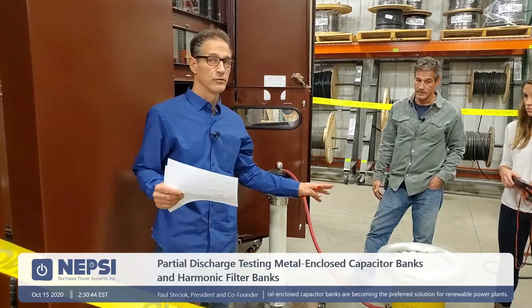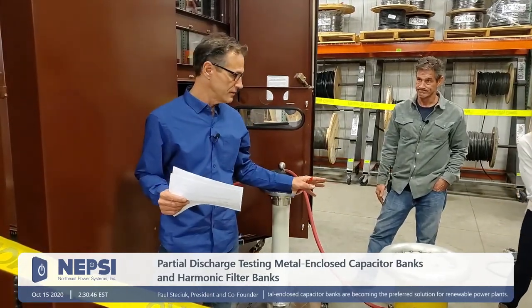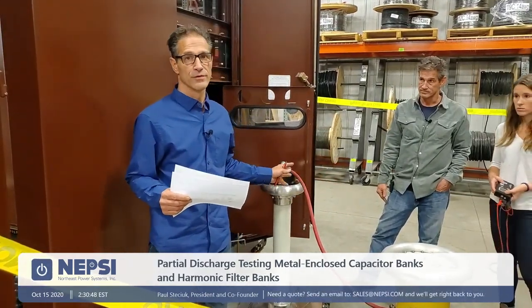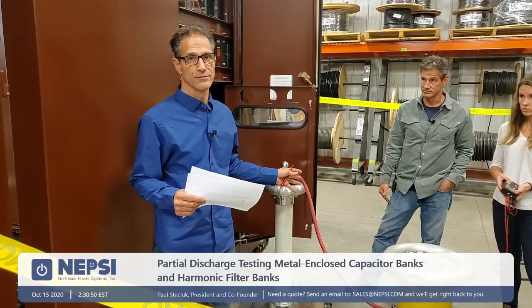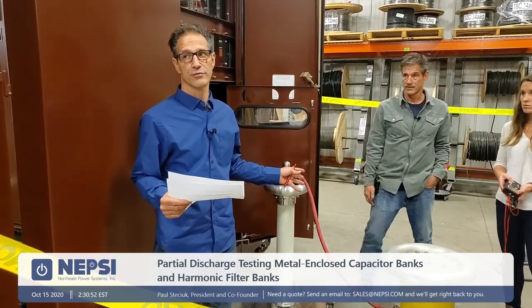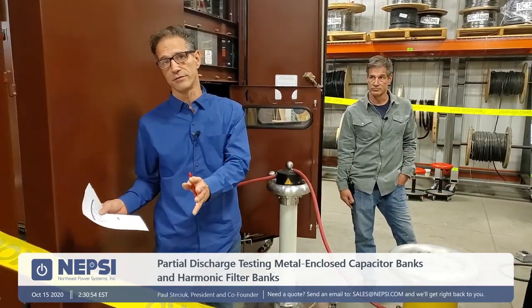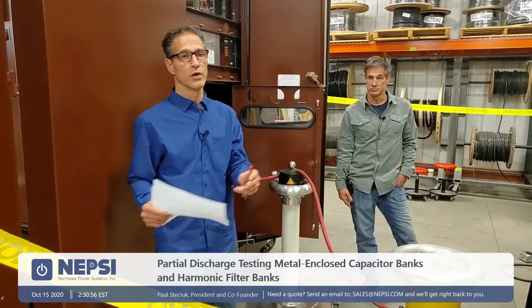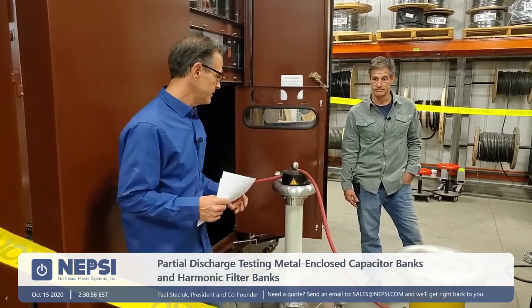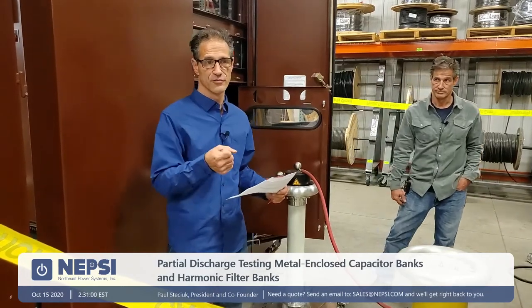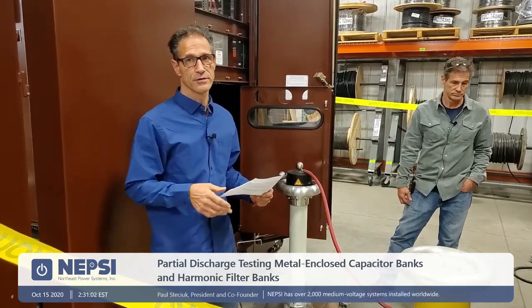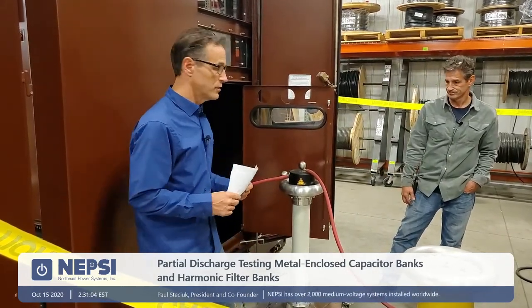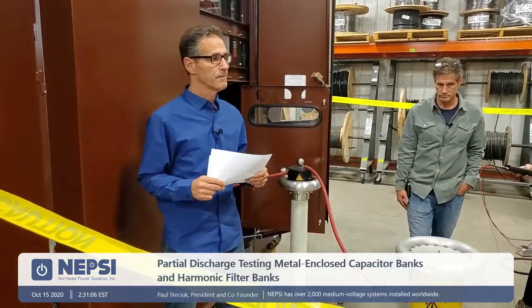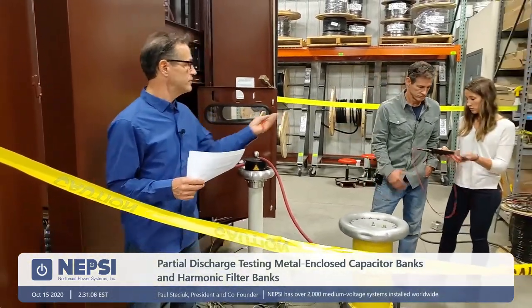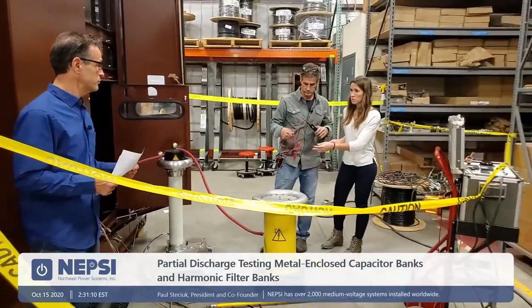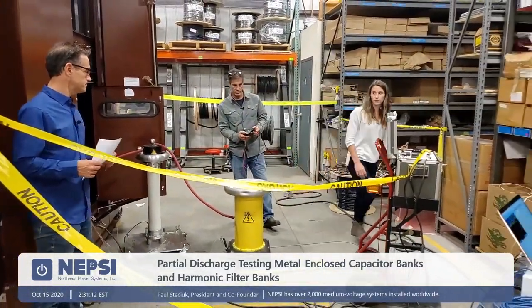So I might add that when we're doing the test here, the test equipment is highly susceptible to noise within the plant, electrical noise within the plant. We actually have to tell people to stop their work for a few minutes while we conduct this test. So we will see drills and saws going in our test instrument when we're running it. So everything is basically shut down here. So we'll start the test procedure. Pete and Jessica will do that test.